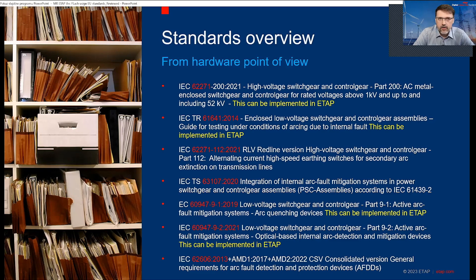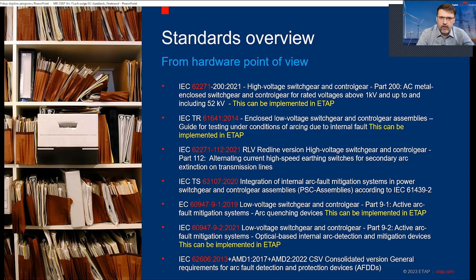There is also arc detection — optic detection systems, which I'll call IEC 60947 as well — and you might also implement it in ETAP as one of the solutions. At the end, we have AFDD, the arc flash detection device. More commercially based, this is a small device — the size of a miniature circuit breaker — which detects serious arcs in circuits limited, I think, to 63 amps and lower to 16 amps.